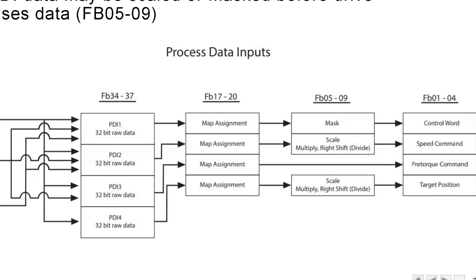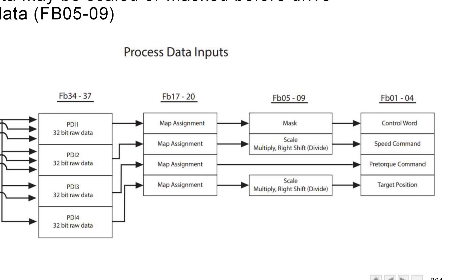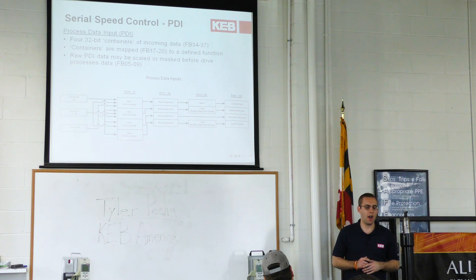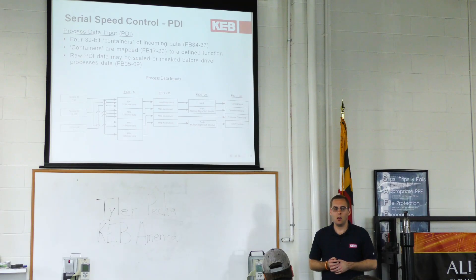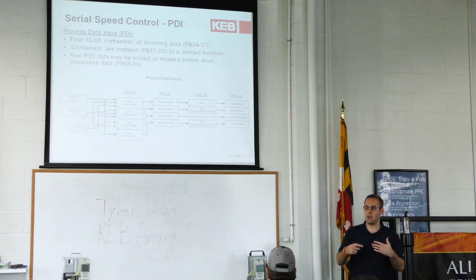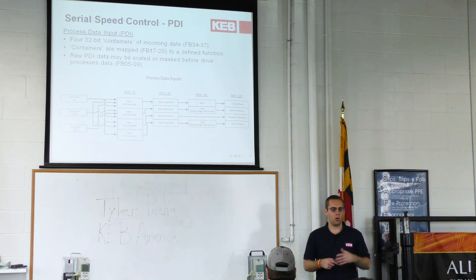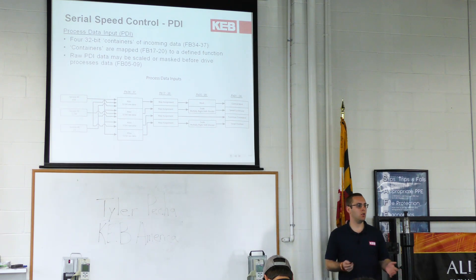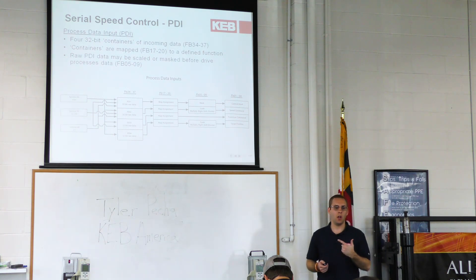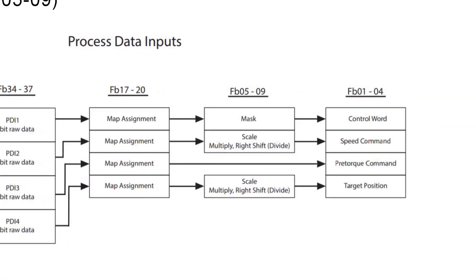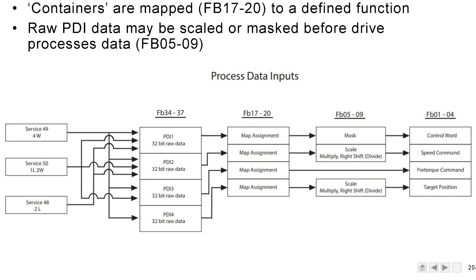Once the data gets its assignment, it's either going to be masked or scaled. Depending on what's coming over from the controller, it may say we don't need to do any scaling. But in the case of the speed command being sent over, it's a raw value — it needs to convert that into something useful the drive can interpret. The value coming over from the controller is unitless, and the drive will do math to scale it to an RPM value. Ultimately it ends up in parameters FB01 through FB04: the control word, the speed command, the pre-torque command, and the target position.